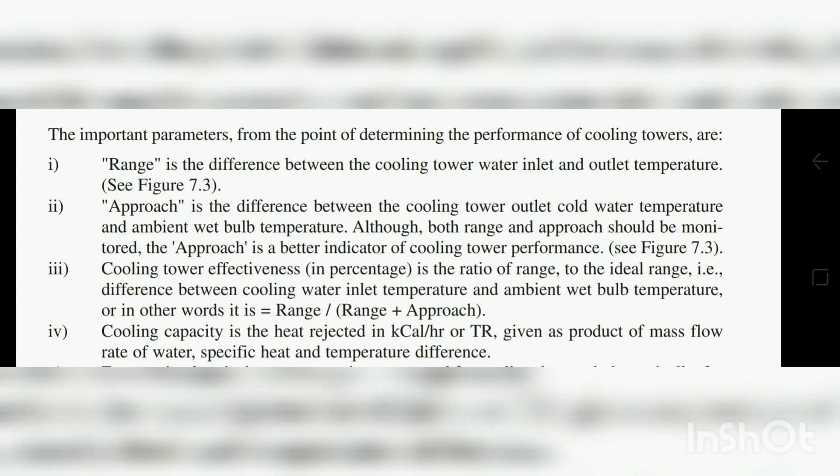Cooling tower effectiveness is defined as: Range divided by (Range + Approach). Range is what we are actually achieving, and Range + Approach is what we ideally want to achieve. In terms of heat transfer, it is the ratio of actual heat transfer to ideal heat transfer. The cooling capacity is the heat rejected in kilocalories per hour, calculated as mass flow rate × specific heat × temperature difference, i.e., mCpΔT.